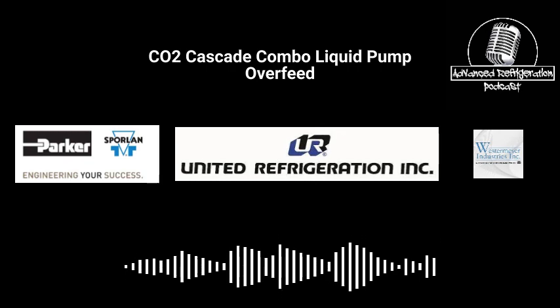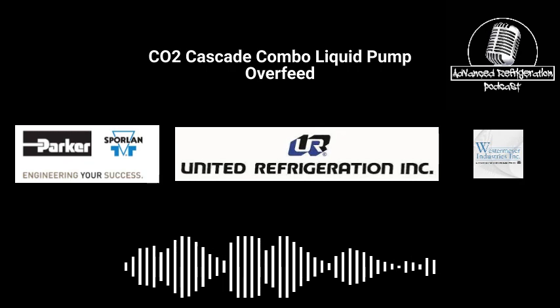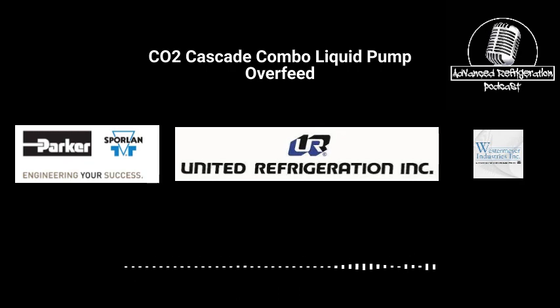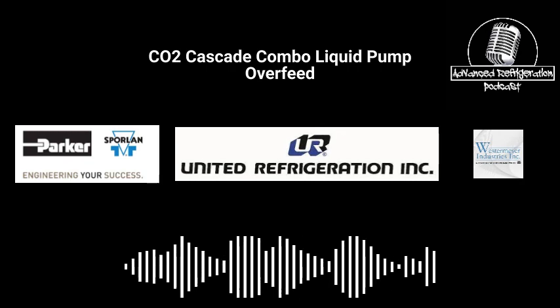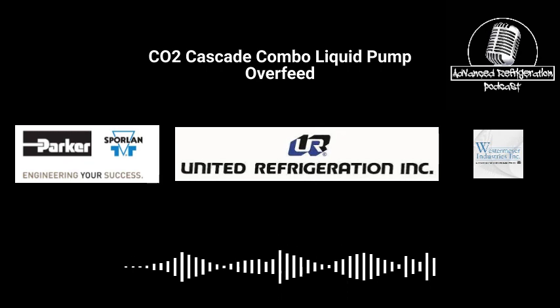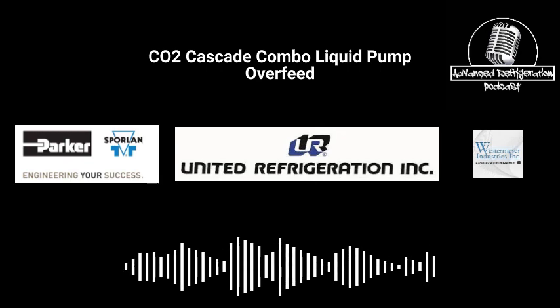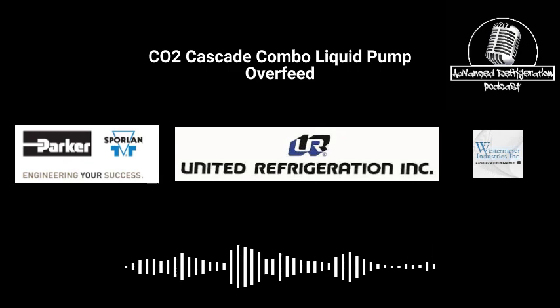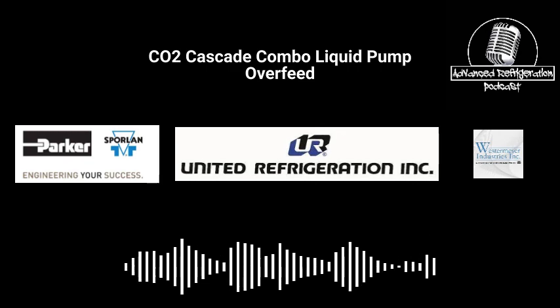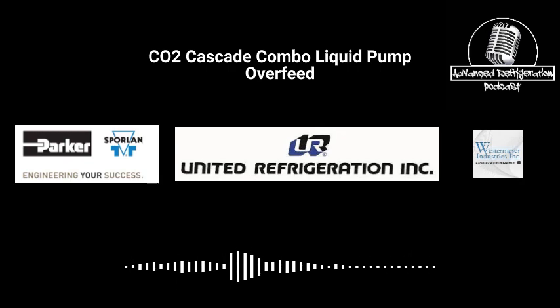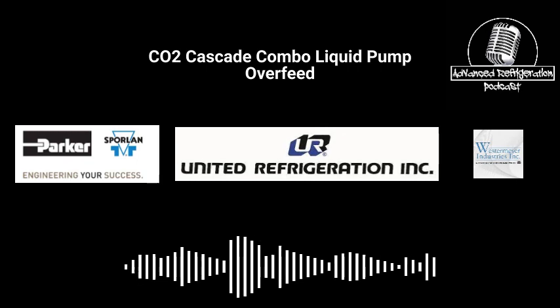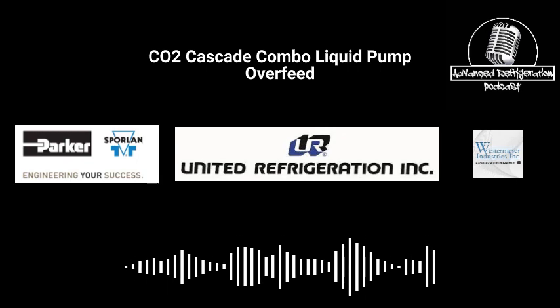So back to this. If you're gonna be using the cascade style with liquid pumped overfeed, you're gonna have either stepper valves or pulse valves on a low temp. You're gonna be a standard DX style, like you have a compressor compressing it and pushing it down. You're going to be running the suction pressure anywhere from 200 to maybe 220. You're going to be running like a normal DX refrigerant would, basically.